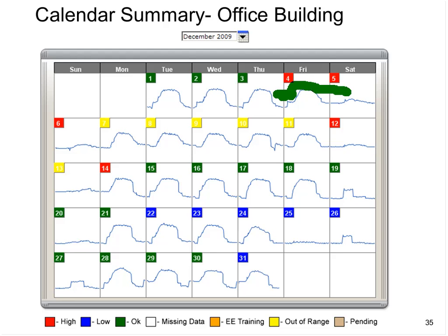So he kept the heat running at a higher level because the building couldn't recover to a normal level if it shut down in its normal fashion.